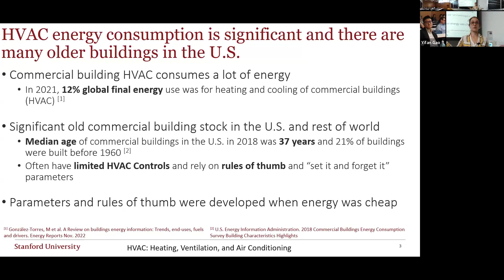This figure shows the outside air conditions at a site in Texas during last summer. The blue line represents the amount of water in the outside air during that period. The red line represents one of these set it and forget it parameters, the amount of water in air at the lowest point in the air conditioning system, which is 55 degrees Fahrenheit, usually the rule of thumb. During this period, on average we needed about 38 kilojoules per kilogram of dry air to cool the air down to 55 degrees.